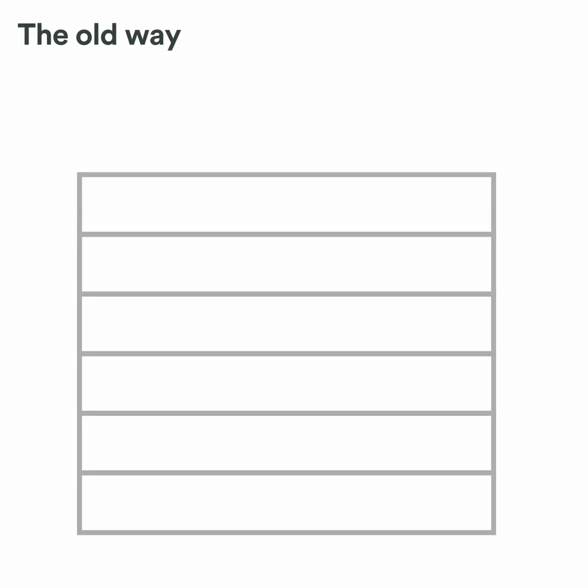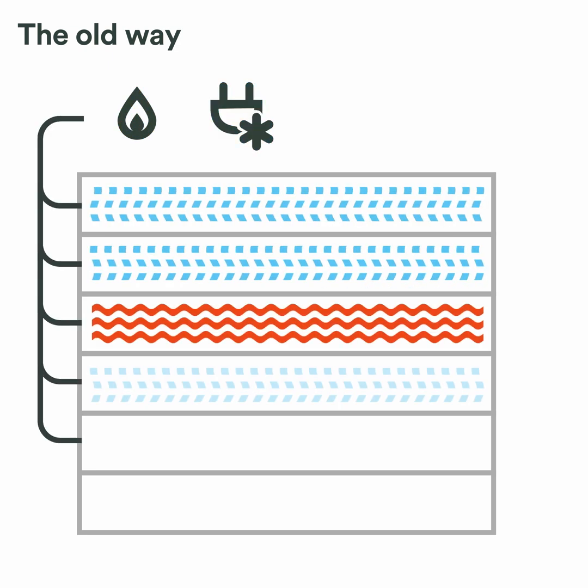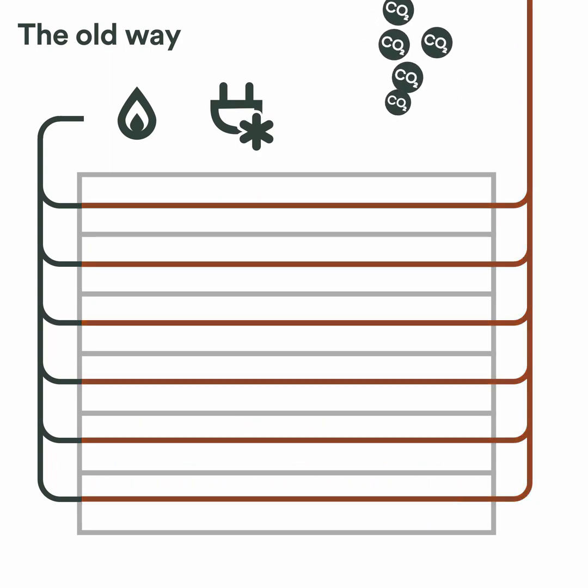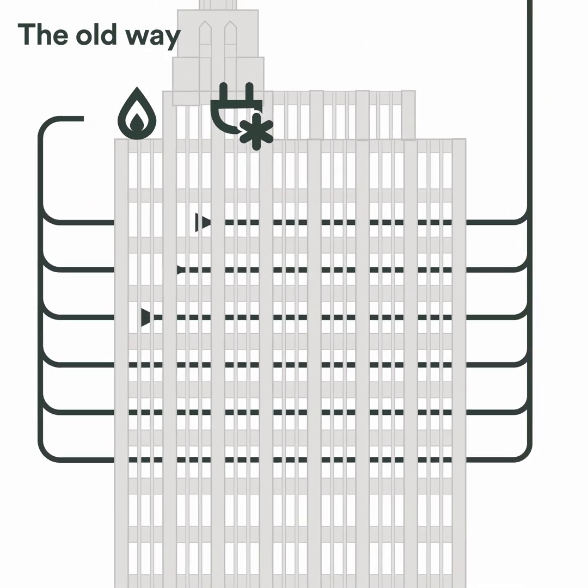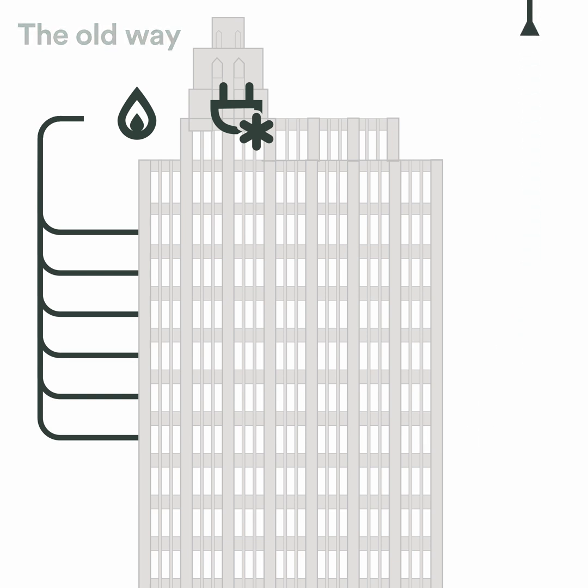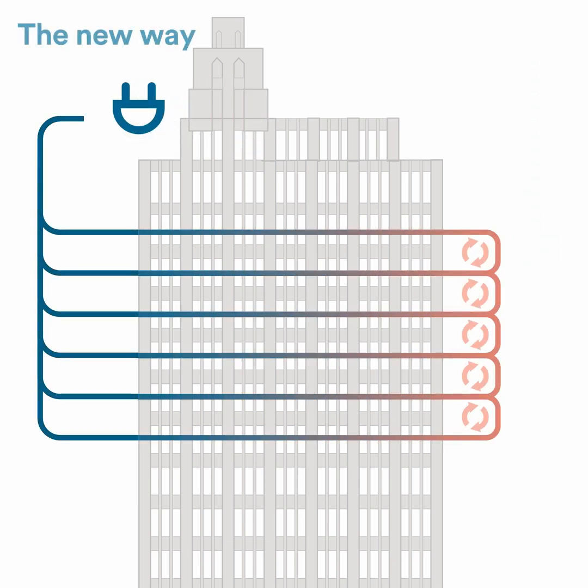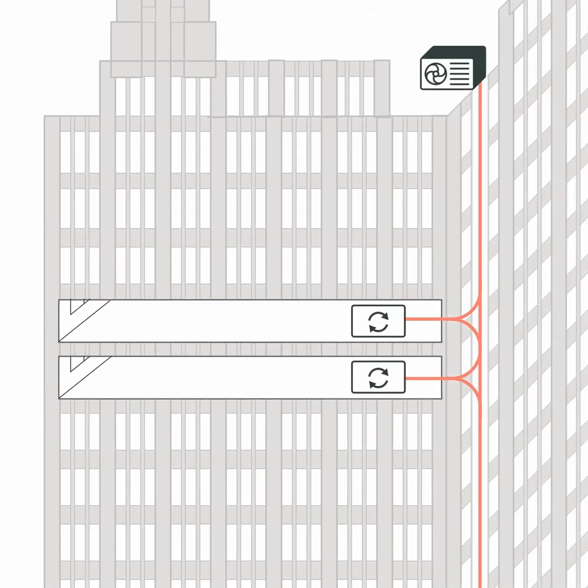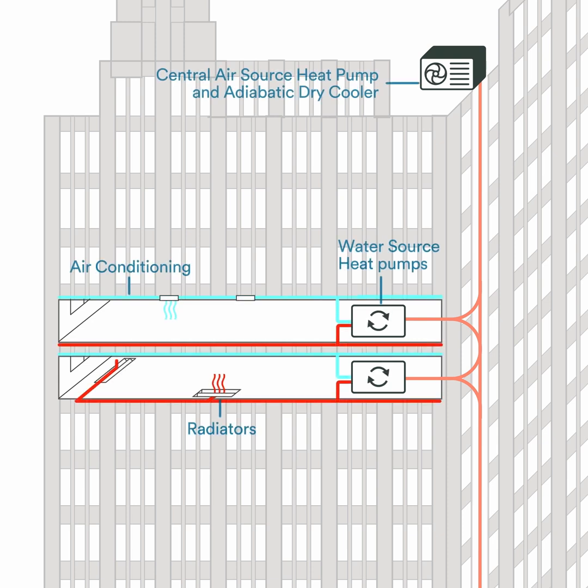Conventionally, electricity or natural gas is used to heat or cool a building and satisfy varying tenant demands across each floor, and excess heat is rejected into the atmosphere. Instead, HSP's project shares heat between spaces, dramatically reducing energy use and carbon emissions. Heat is shared through a water-based thermal energy network using water-source heat pumps, plus new and pre-existing pipes to transport heat within and between the building's floors.